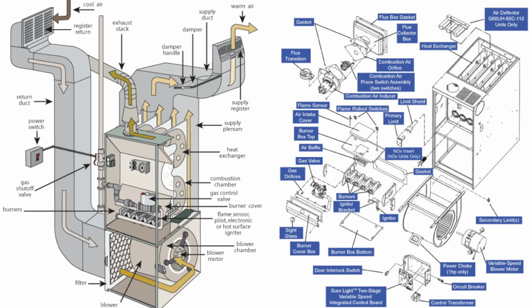You have your return duct, and in this picture, this is galvanized ducting. There's no flex duct that you see here. This is all galvanized because it's mainly in a basement. As you go down, all of your furnaces by city code are going to have a power switch, an on and off switch to kill power. You're also going to have a gas shutoff valve. These are all going to be by city codes. And if you notice, you can see the gas line running down right there by the gas valve shutoff. That allows the service tech and the homeowner, if there's any emergency, or the fire department, to cut the gas off to the furnace in the event of a possible defect or a fire.